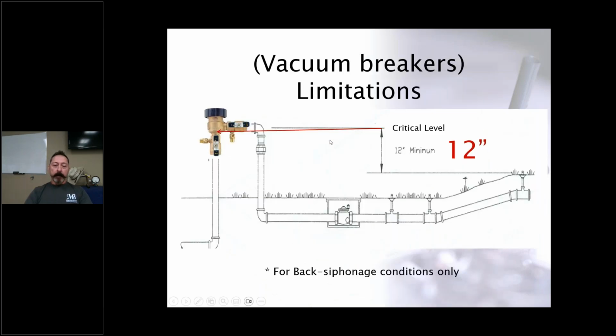Some vacuum breakers that are limited to backsiphoning conditions only cannot be subject to back pressure. So the backflow preventer itself has to be the highest part of any downstream piping. If there's elevation downstream, or heat, or pumps, vacuum breakers will not function properly. So there are limitations on some of these different types of valves that we have to be cognizant of when we're observing or identifying these backflow preventers in our system.